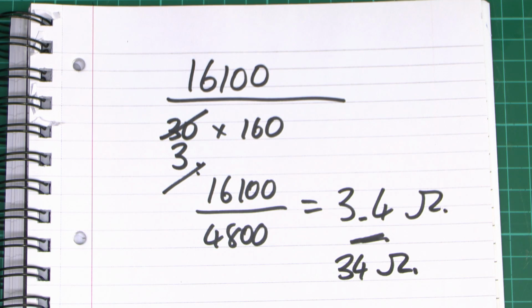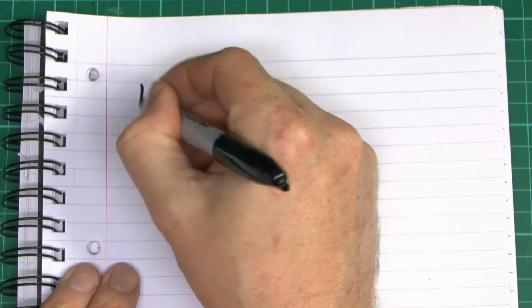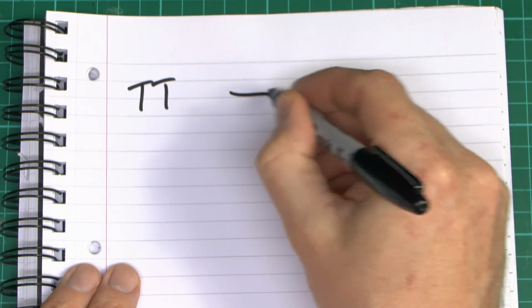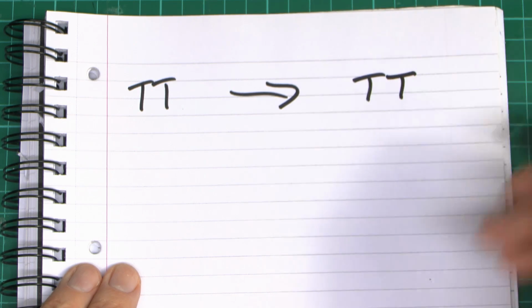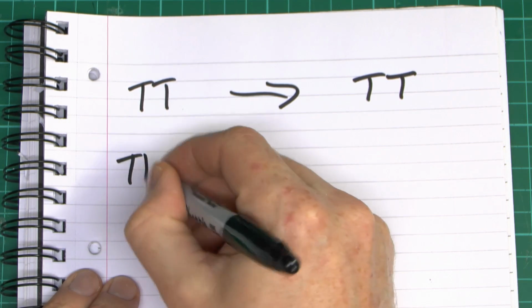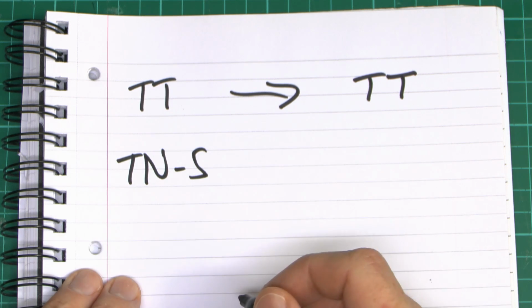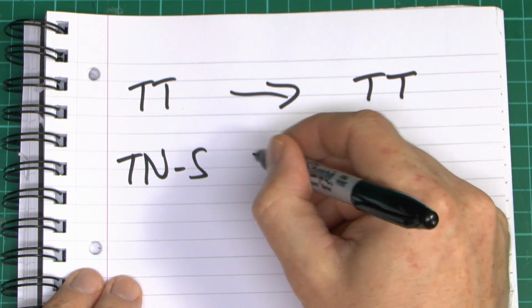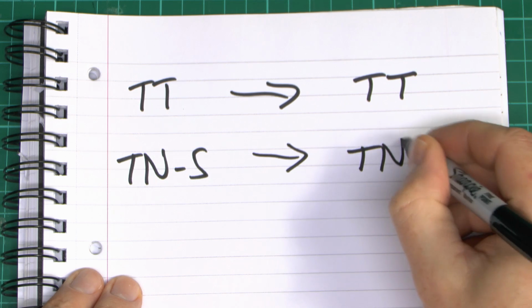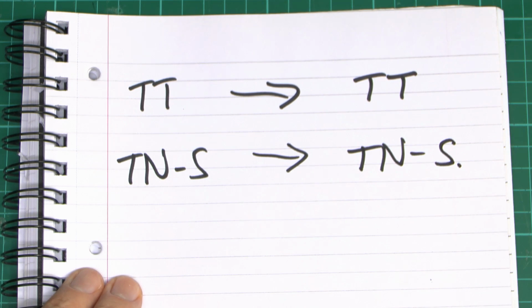So, although in theory you can use that option 2 there, in reality it's going to be impossible, because you won't be able to get the electrode resistance low enough. Simply the fact that getting things in this sort of single-digit ohms is next to impossible. So in summary then, depending what earth system you have, these are your options. If it's a TT installation, then basically you're going to be using it as what you've got there, no particular change. For TNS, typically older lead-covered cables coming in to the older properties, then again you can use TNS just as you would before.